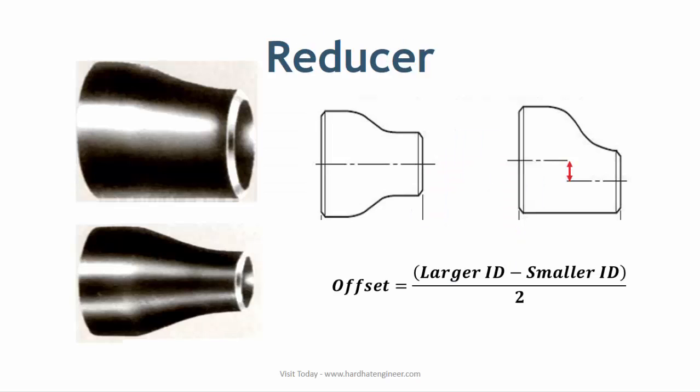Reducers are used to change the size of the pipe. There are two types of reducers used in piping: concentric and eccentric. In concentric reducers, the center of both ends are on the same axis, which maintains the centerline elevation of the pipe.